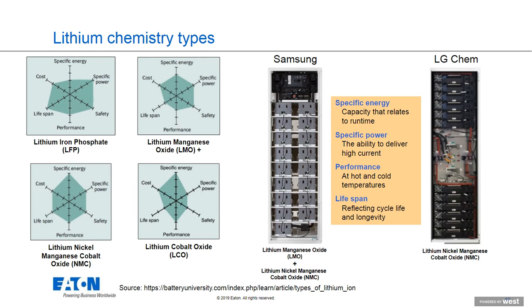This slide shows 4 different lithium chemistries and their performance in terms of specific energy, which relates to backup time; specific power, which relates to how quickly they can discharge a lot of energy; safety; performance at high and low temperatures; and the actual lifespan of the lithium. Looking at the 4 charts on the left side of the slide, you can see there are some differences between the chemistries.